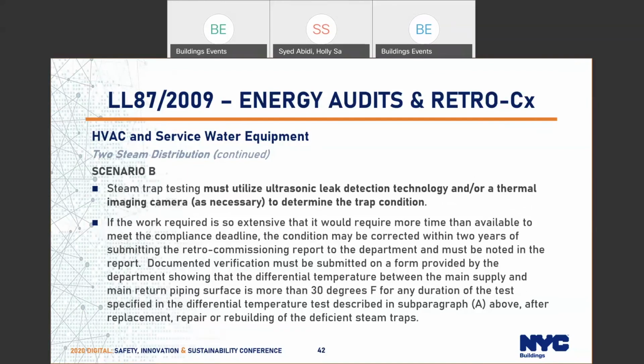There is a provision that has been added to the rule amendment if the work required is so extensive that it would require more time than available to meet the compliance deadline. The condition may be corrected within 2 years of submitting the retro-commissioning report to the department and must be noted in the report. Documented verification must be submitted on a form provided by the department showing that the differential temperature between the main supply and main return piping surface is more than 30 degrees Fahrenheit, for any duration of the test specified in the differential temperature test described in subparagraph A above, after replacement, repair, or rebuilding of the deficient steam traps.